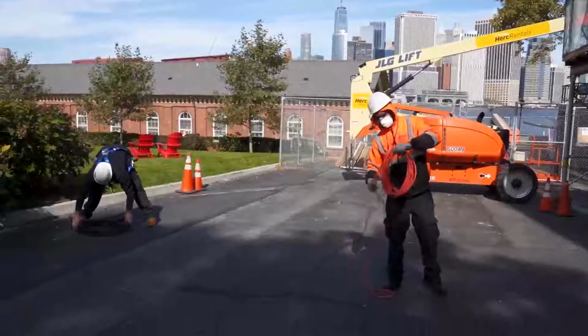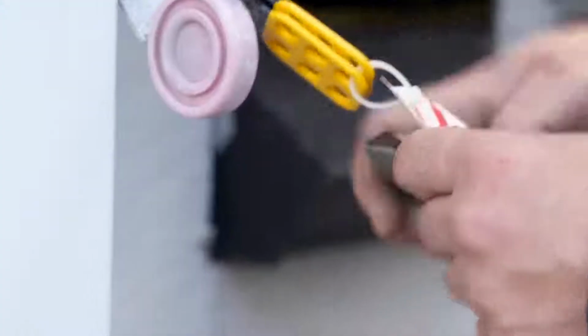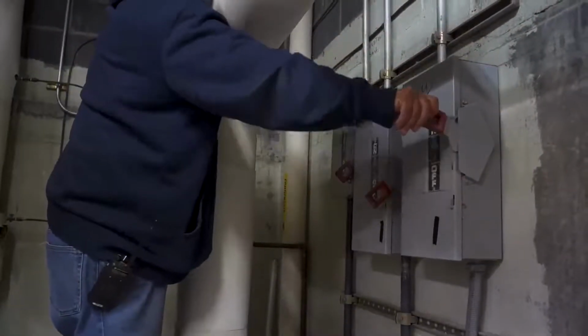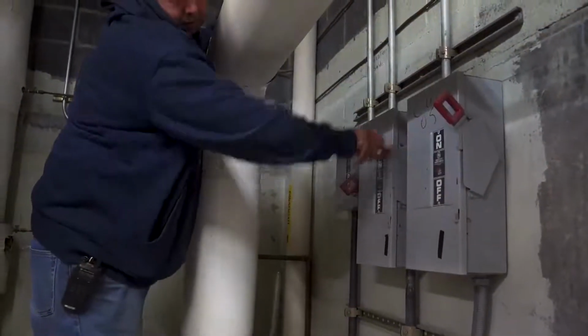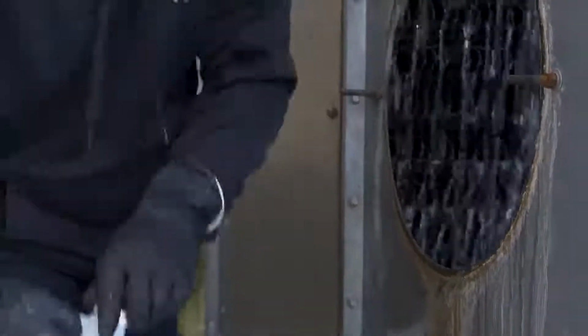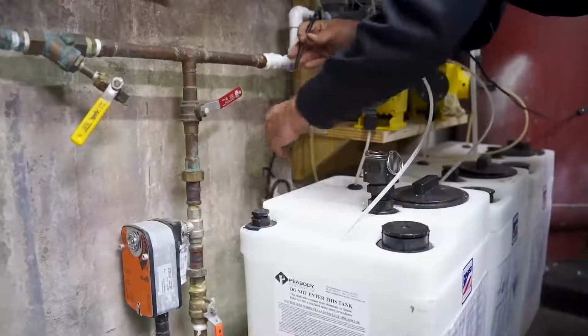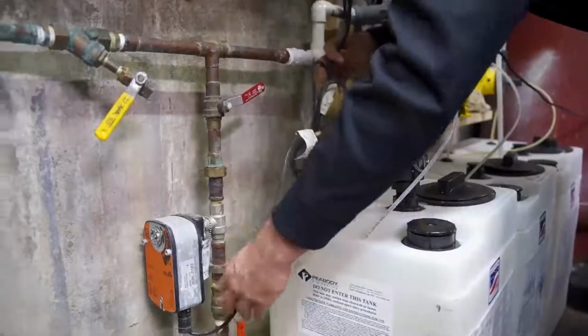Bag and remove garbage into building's dumpster. Remove the locks and tags and have the customer re-energize the system and get the tower and units back online. Add retreatment chemicals to the tower, one at a time, as prescribed in the job notes. Remove the last tag on the tower fan's controls, but leave the disconnect in the off position. Don't forget to plug the bleed valve all of the way in.